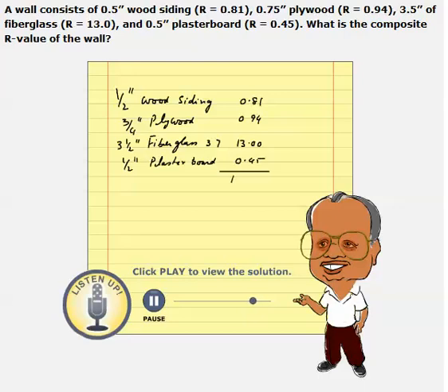So when you add these up, you get 15.2, which means the composite R value of this wall is 15.2 degrees Fahrenheit foot square hour over BTUs.